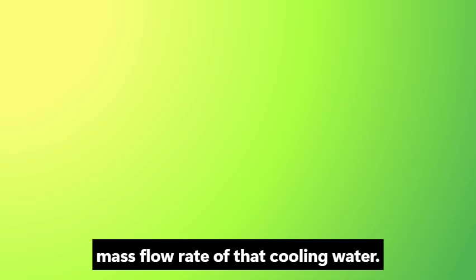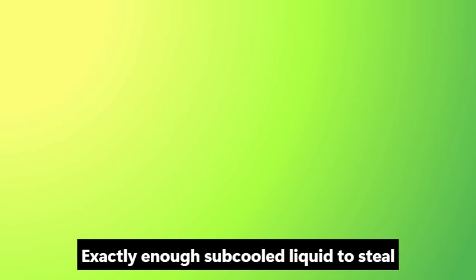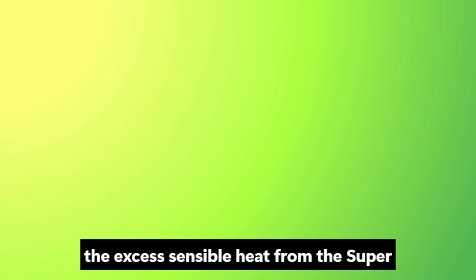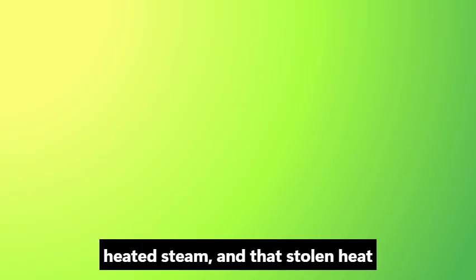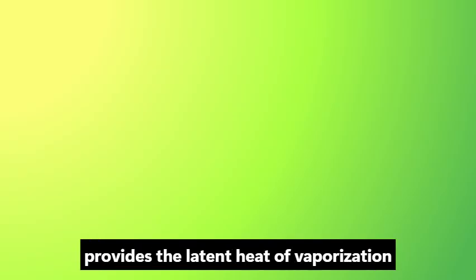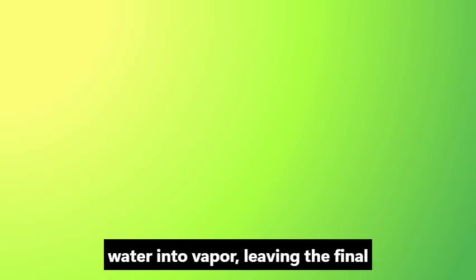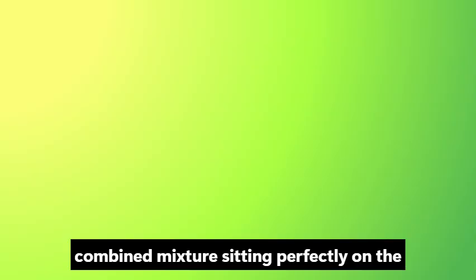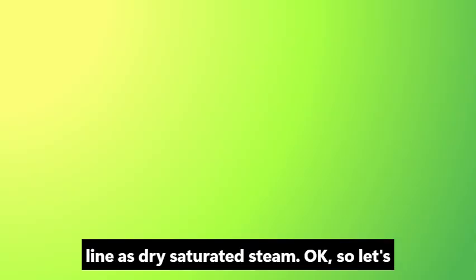Wow. So we have to calculate the absolute perfect mass flow rate of that cooling water. We need exactly enough subcooled liquid to steal the excess sensible heat from the superheated steam. And that stolen heat provides the latent heat of vaporization needed to instantly flash the injected water into vapor, leaving the final combined mixture sitting perfectly on the line as dry, saturated steam.